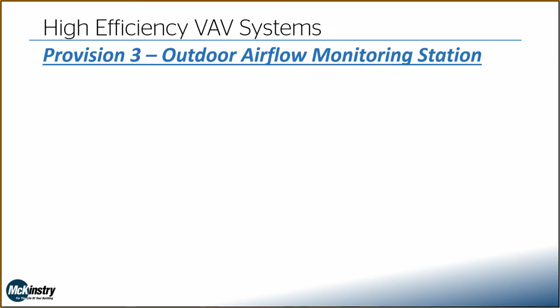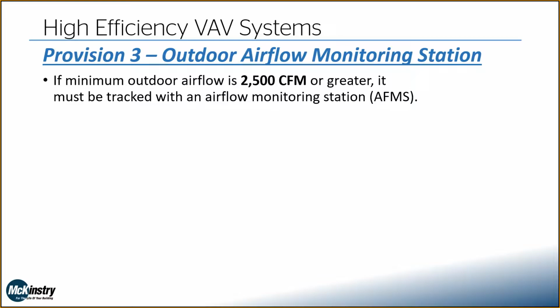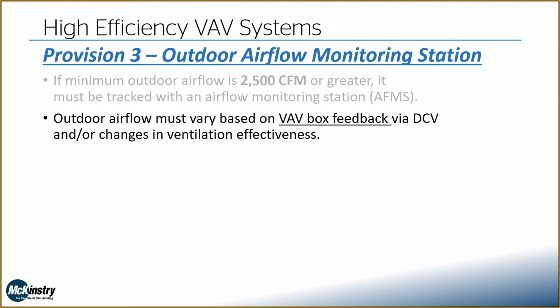The third provision, outdoor airflow monitoring. If your air handler has a minimum outdoor airflow of at least 2,500 CFM, you have to track that with an airflow monitoring station. Additionally, that airflow has to vary based on some VAV box feedback. So if you're doing demand control ventilation out in your space, it also needs to account for changes in ventilation effectiveness. If the majority of your VAV boxes are in heating mode, that's going to have a different ventilation effectiveness than boxes in cooling mode, and your system has to account for that. The code isn't explicit on how to account for that, but this is just describing the general intent.